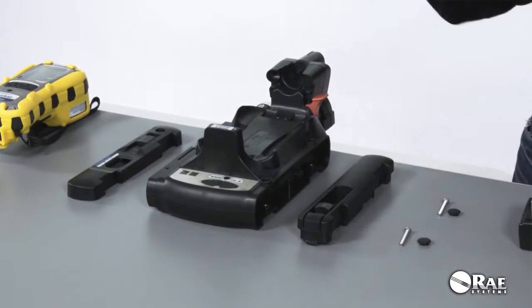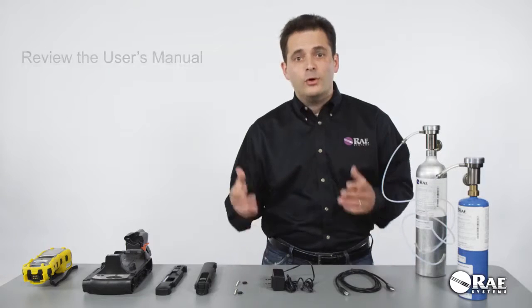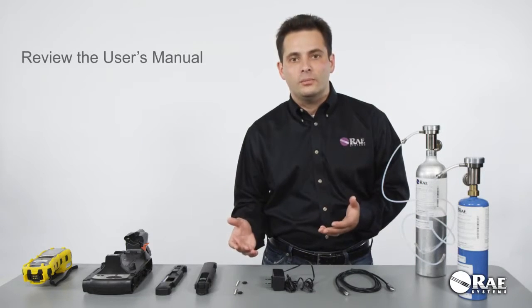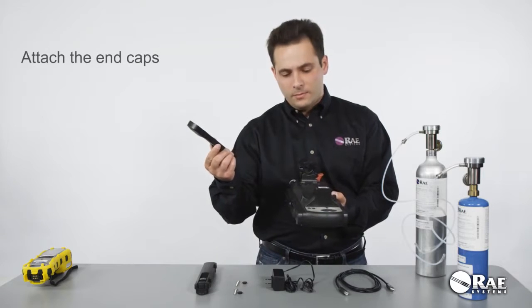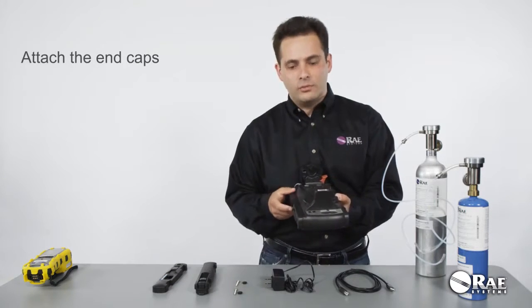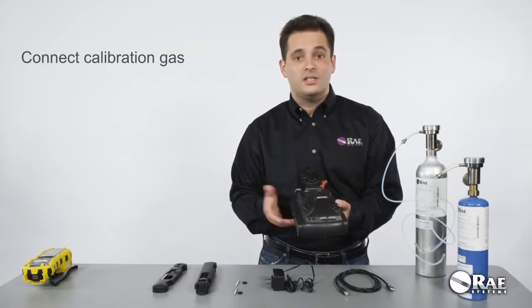The AutoRAE 2 cradle that we're going to look at is for MultiRAE pumped instruments. Before you start the setup process, please make sure to review the user's manual. The setup process is very simple. All you need to do is attach the end caps to the cradle, fix them with the screws, then power the system and connect calibration gas. It's that easy.